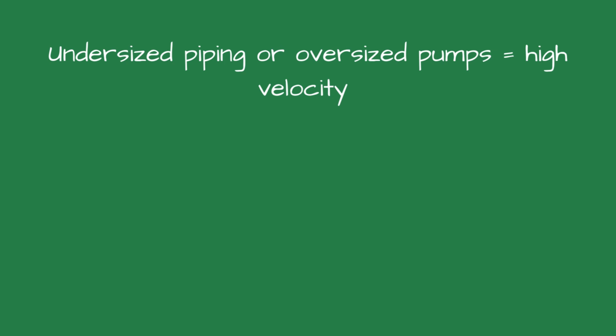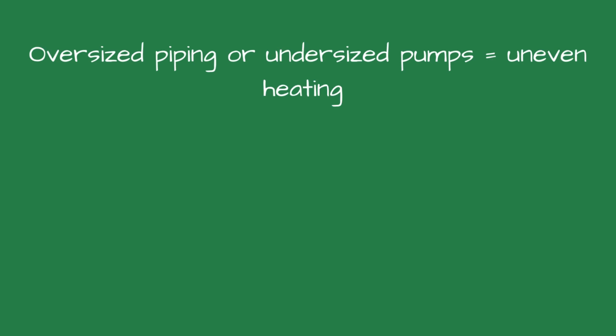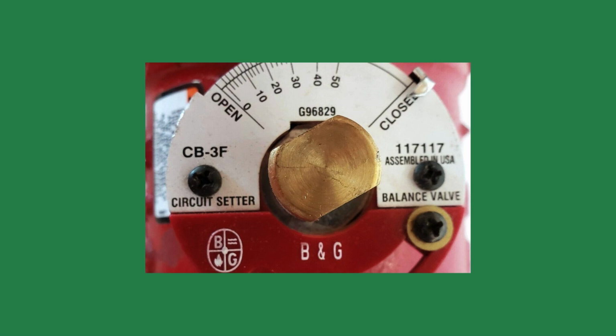Water velocity ties directly into pipe sizing and pump selection. Undersized piping or oversized pumps can result in excessively high velocity. Oversized piping or undersized pumps may produce sluggish flow, leading to cold spots or underperforming zones. Uneven flow due to poor velocity can lead to some zones overheating. Maintaining the proper velocity ensures even heat distribution and better system balancing.